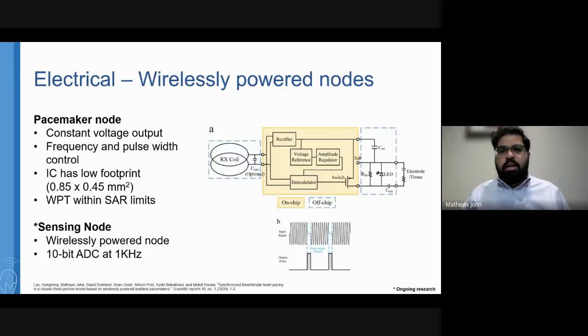An oversimplified look at what's happening inside the node: the radio frequency comes into the node, gets accepted by a matching antenna, and then gets rectified. A specific voltage reference creates this constant voltage output, and once the voltage reference is met, a switch goes in and out, stimulated based on the input signal, to create a pulsing output. That output goes through an electrode-tissue interface into the heart, and that's what causes the heart to pace. You do see an LED in here, which is not required for pacing—it's mostly there for visualizing that we have an output, which helps with testing.